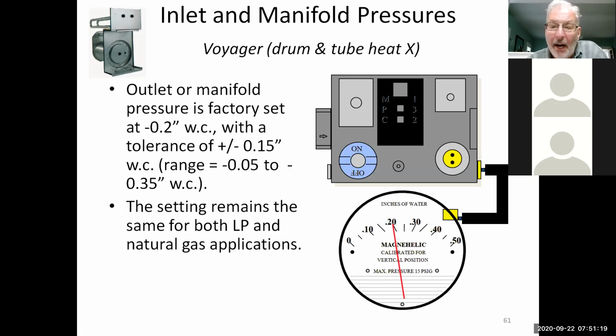Okay. Natural and LP is the same pressure. So the only difference between natural and LP on these is the orifice. We changed the orifice on them. Otherwise, the gas pressures stay the same. They're negative 0.2 on all of them.